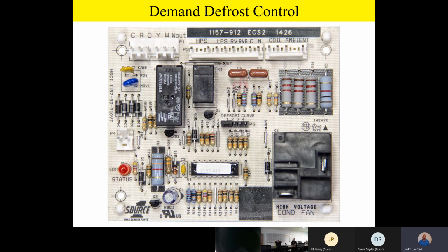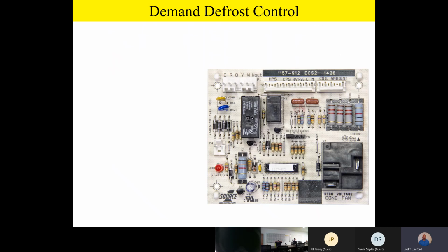Well, okay, team, let's go ahead and jump into this defrost control then, this demand defrost control. As I said, this is a very common type of control. As a matter of fact, most manufacturers anymore use a demand defrost control because it is more efficient, because you're not defrosting quite as much throughout the day. It has a tendency more to defrost on an as needed basis because it's looking at outdoor temperature and coil temperature. And so it has more of a tendency to defrost as needed, not so much just strictly on a time basis.